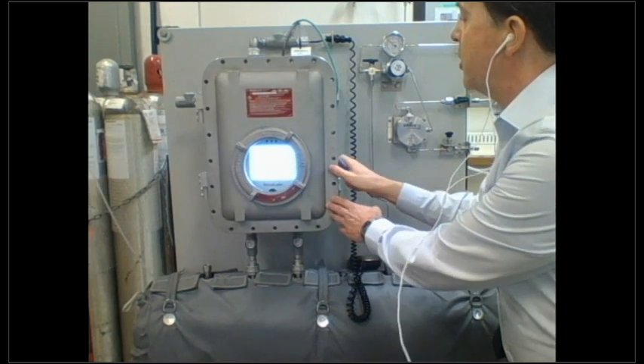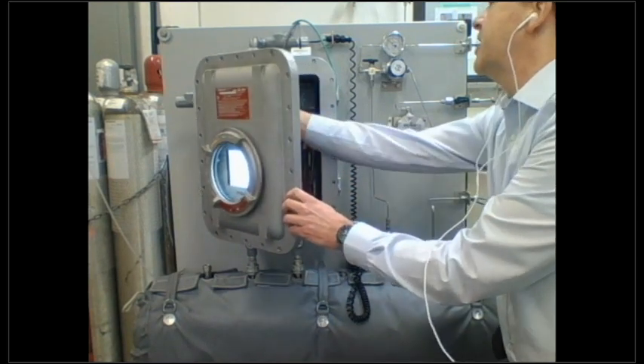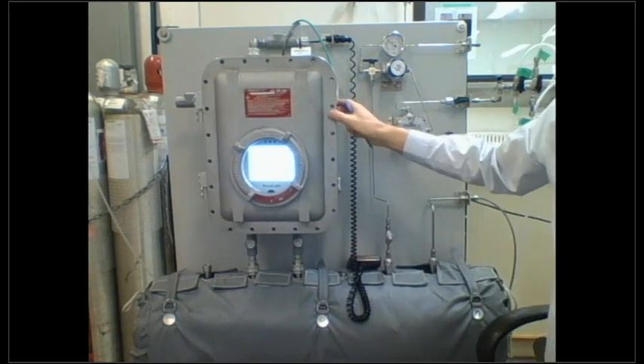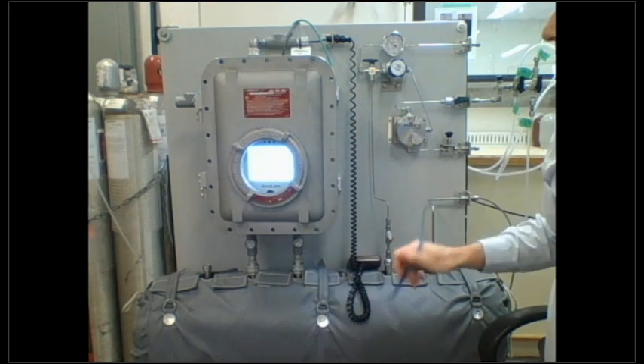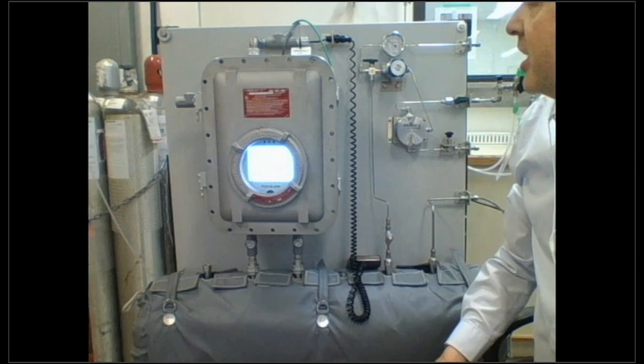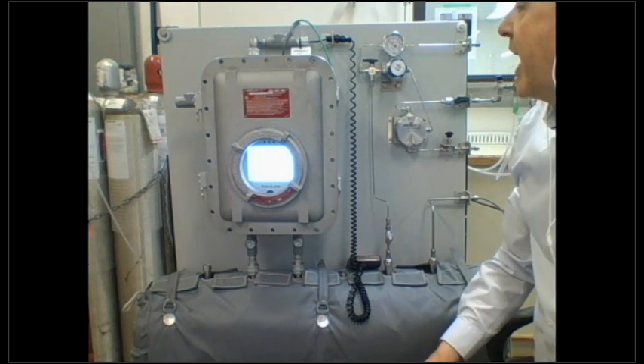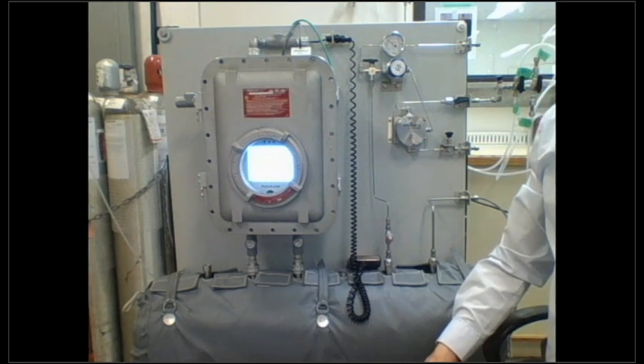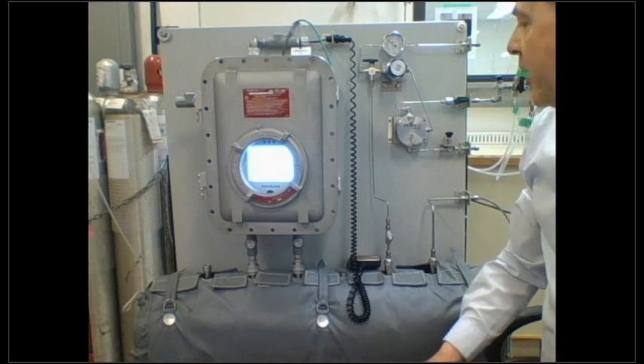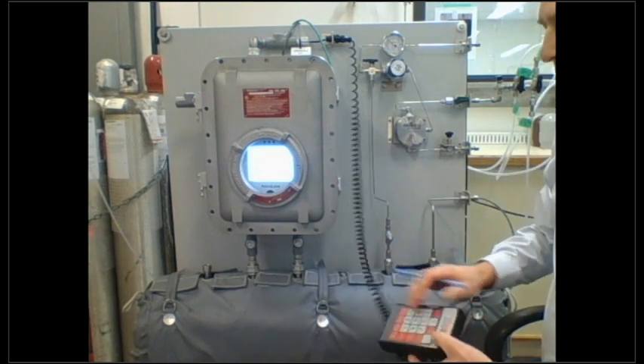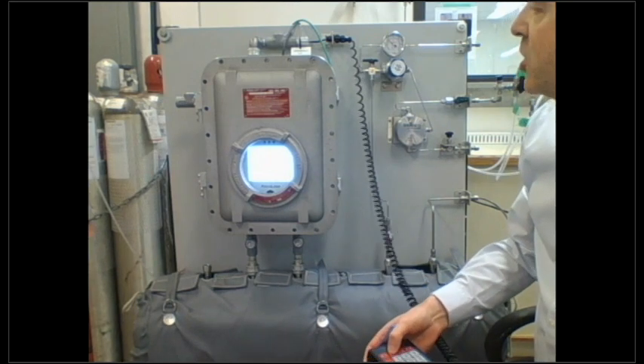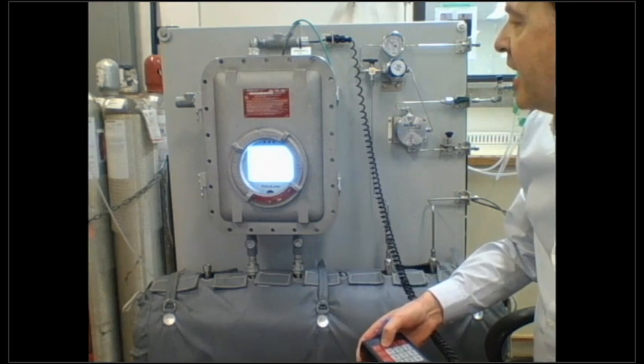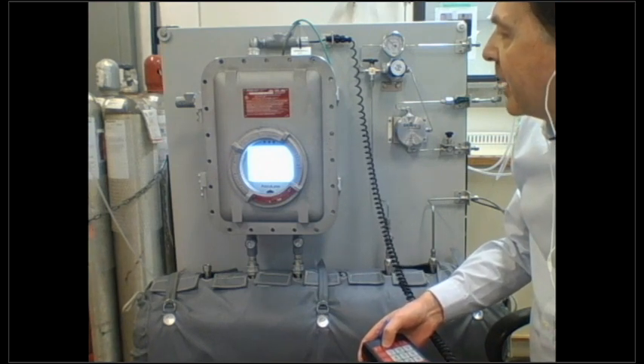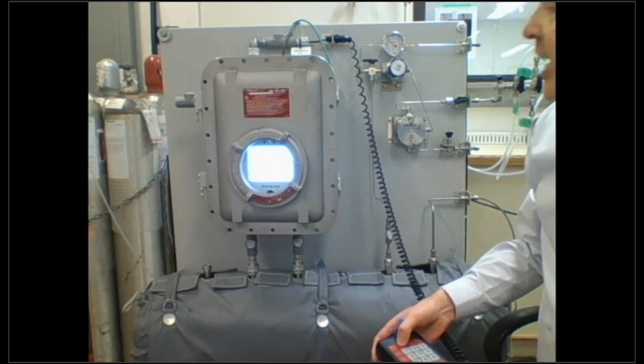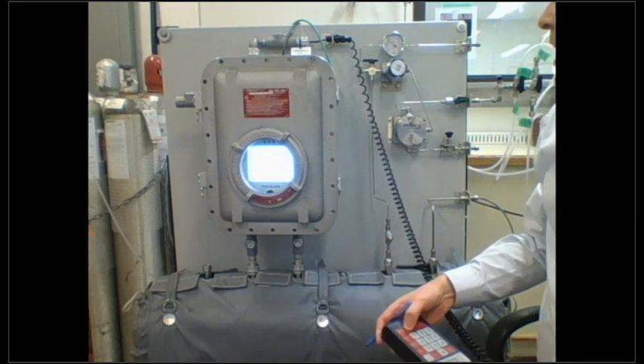So in terms of the local user interface, again, I do apologize for the inability to see that screen very well, but basically what it shows you on the home page is the concentrations of your gases, the pressure and temperature of the cell. These are important things that you would want to look at. And then it has a scrolling system through a keypad where you can use page scrolling to look at alarms, the status of various outputs, do your calibrations or validation checks, look at some of the parameters associated with the laser, do a little bit of configuration. So basically, the concept behind the local user interface is to be able to do most of the basic things that you would need to do for regular maintenance and regular operation without having to drag out a laptop.